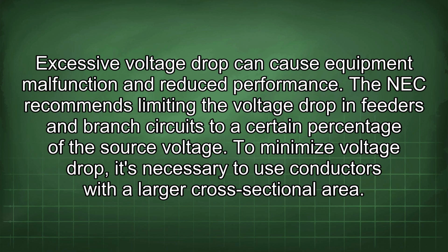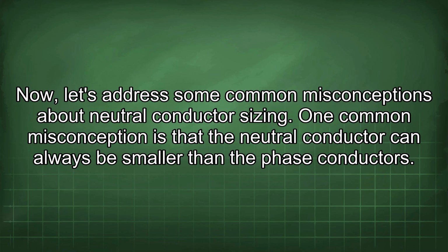The NEC recommends limiting the voltage drop in feeders and branch circuits to a certain percentage of the source voltage. To minimize voltage drop, it's necessary to use conductors with a larger cross-sectional area. Now let's address some common misconceptions about neutral conductor sizing.